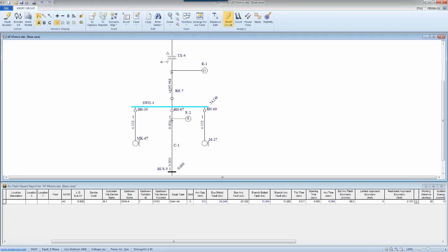So you need a process, you need an approach, you need a few steps in order to translate this value to an arcing current from each branch. You already know the total arcing current for the bus. You need to figure out how to translate that to currents that come from different branches. There could be a few different approaches. I'll look at them as we move forward. But one good method would be looking at this total current, dividing this value by this value, coming up with a percentage value, and then put a percentage value for each branch.